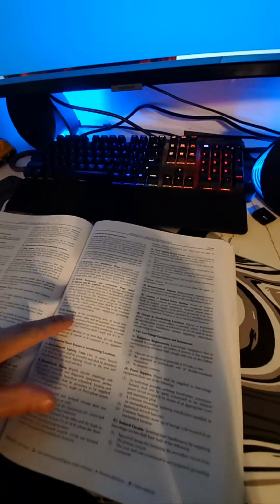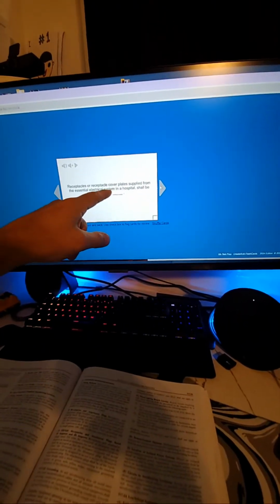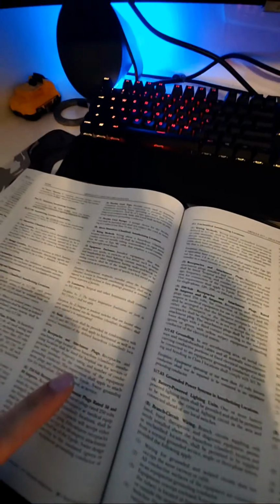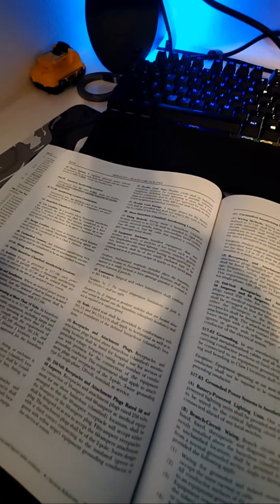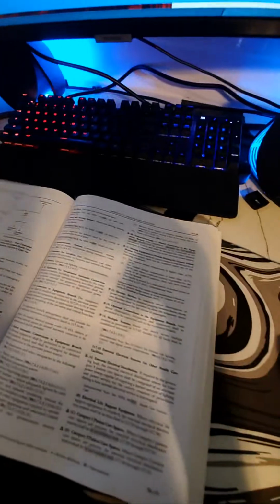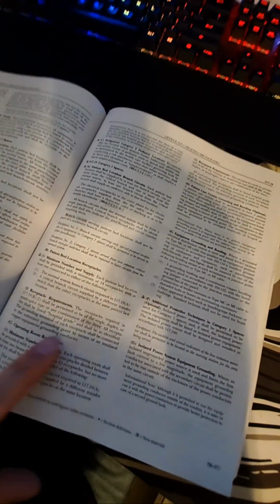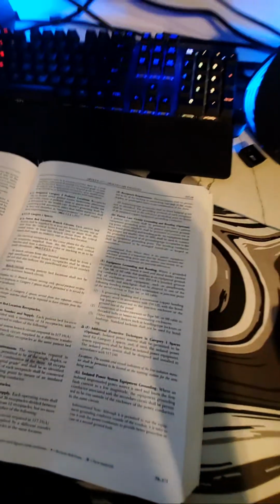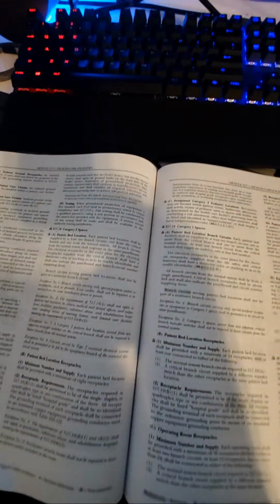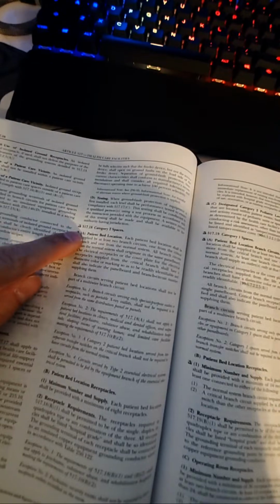Okay. So we're looking for marking, identification, receptacles, and we're looking for essential electrical system. Here's some receptacles, attachment plugs. Let's go back to the beginning of 517. The very beginning. Receptacle requirements. Sorry, just jumped there. Receptacle requirements. But that's going to be for patient beds, see? So we're in A, B, 1, 2. So these receptacle requirements are going to be for the patient beds. You see how that works? So you can't just jump and grab the code wherever you want to.